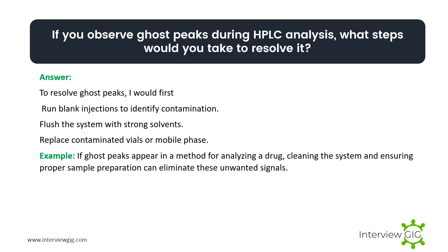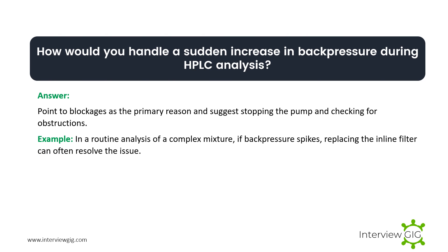If you observe ghost peaks during HPLC analysis, what steps would you take to resolve it? To resolve ghost peaks, I would first run blank injections to identify contamination, flush the system with strong solvents, and replace contaminated vials or mobile phase. Example: if ghost peaks appear in a method for analyzing a drug, cleaning the system and ensuring proper sample preparation can eliminate these unwanted signals.